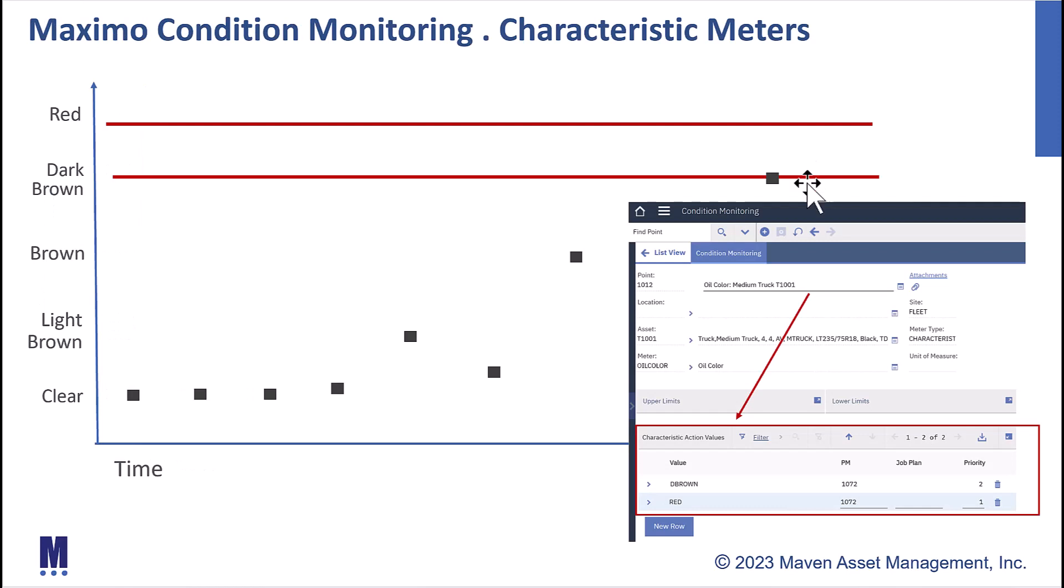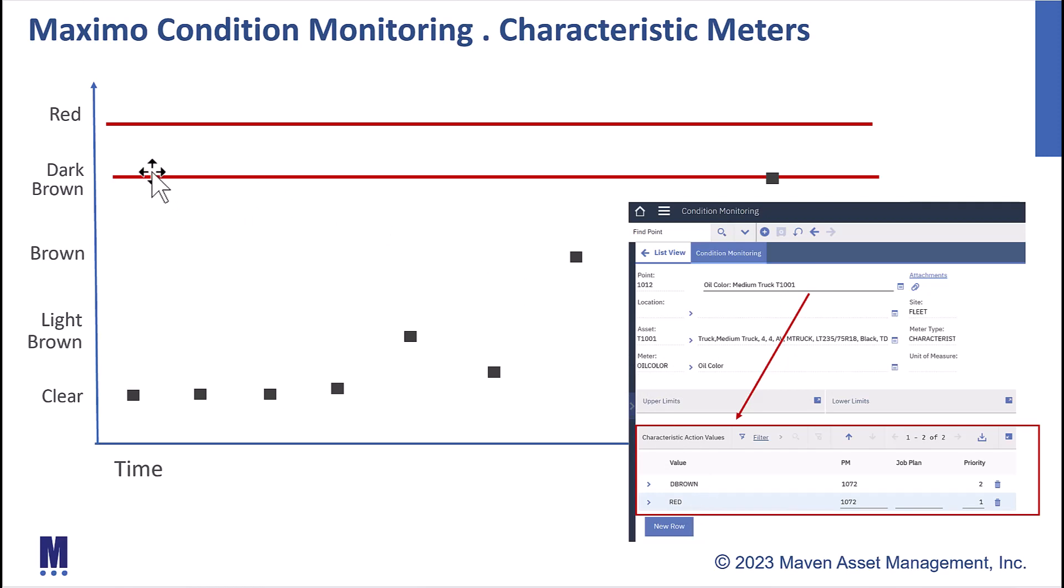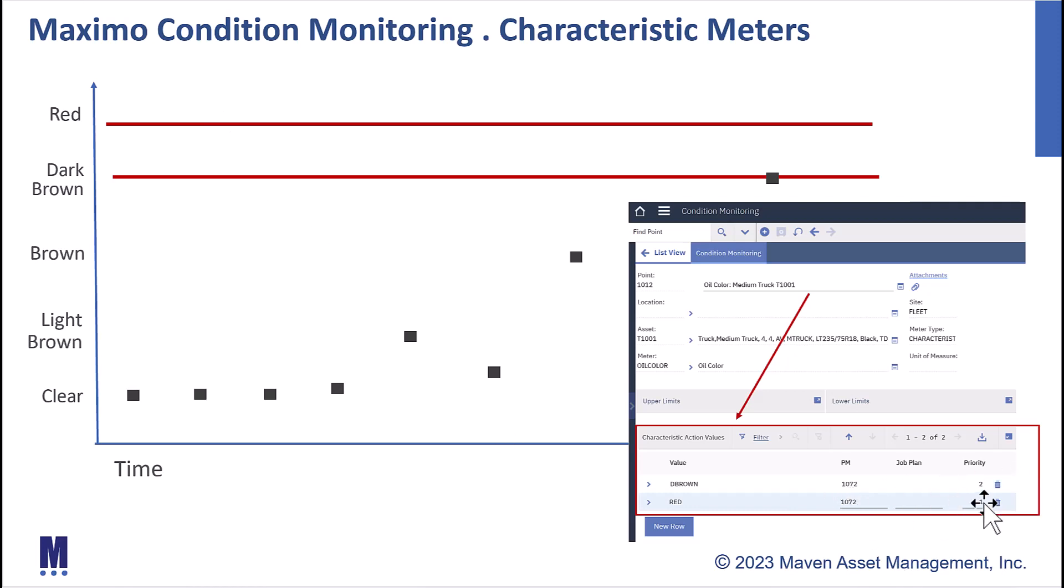So how do we do that? In condition monitoring, we go in, set up a point on the particular asset, on the particular characteristic meter. In this case, it's an oil meter. And we identify what those colors are. The colors are dark brown or red. So if either of these colors are noted from a meter reading, we want Maximo to automatically kick out that PM work order, which is noted down here, along with the associated work priority.